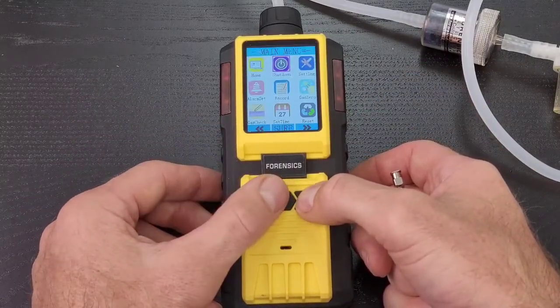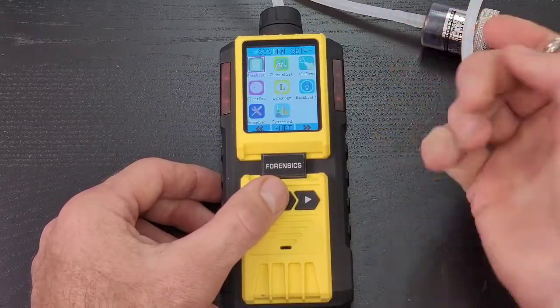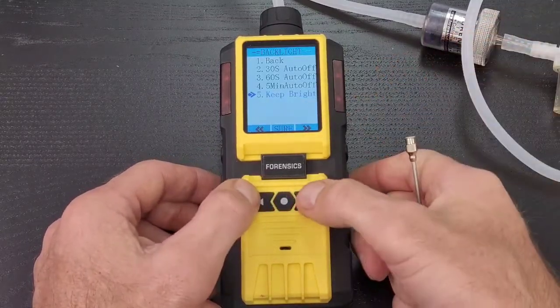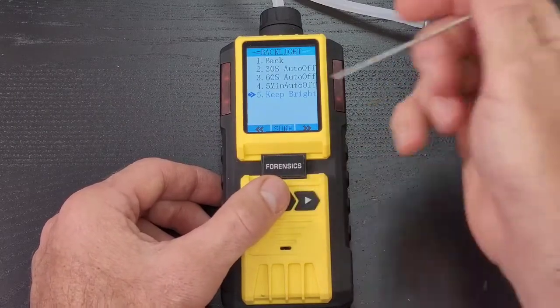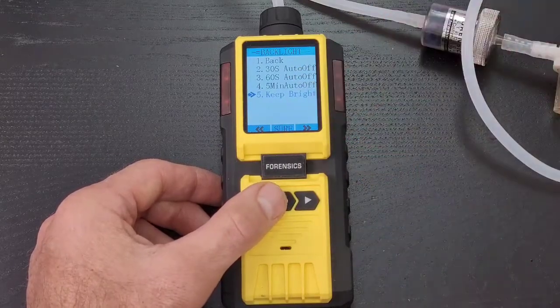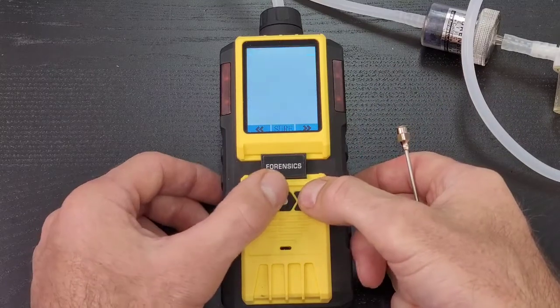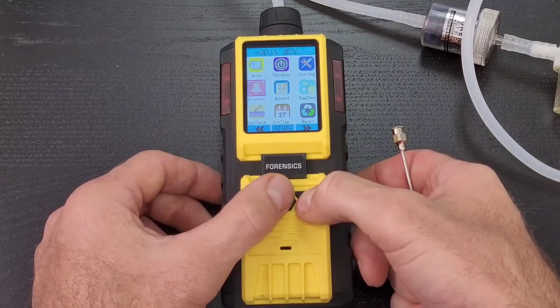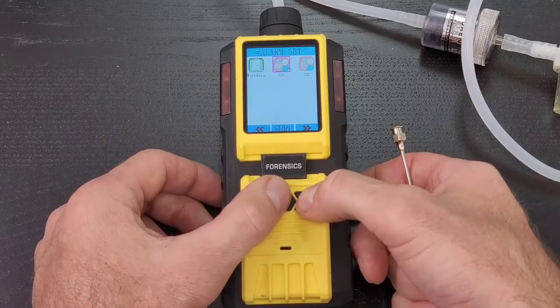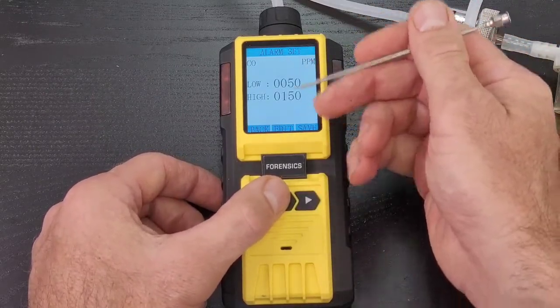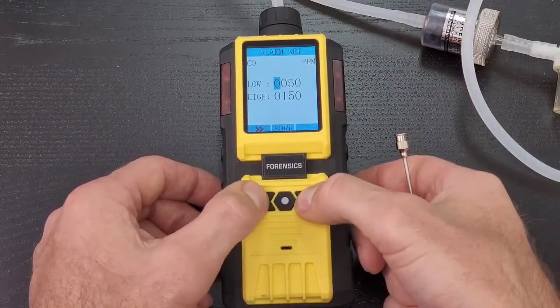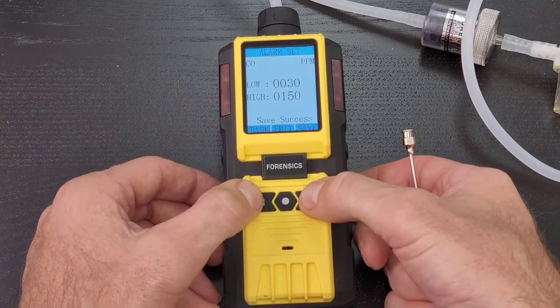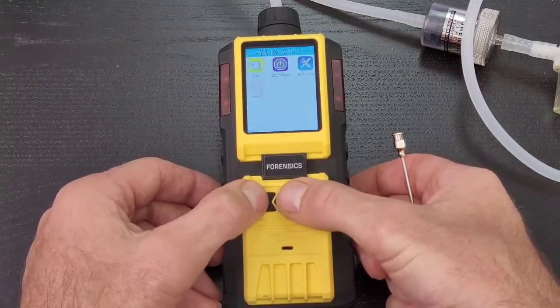Go to your menu. You could close down by shutdown. You could go into settings, and you could do a lot of different things here. For example, one of the things people like to do is the backlight. They want it always on. You can do that. Just keep bright, or you select five minutes, 60 seconds shut off. It's really up to you. If you want to save battery time, you reduce the time. If you don't really care, and you just want it always on, that's the way I like it. I want to keep it bright. That's the way we do it. So you go back to main menu, and then you have other functions, such as your alarm set. You may be doing indoor air quality, and you want to set the alarm for carbon monoxide. You have your low alarm and your high alarm. You may want to put it low down to 30. You see what I'm doing? I'm moving across with the cursor and changing the digits, and then I'm setting and saving. It's quite straightforward, and it's quite intuitive. It's not that complicated. Just play around, and you'll get it.